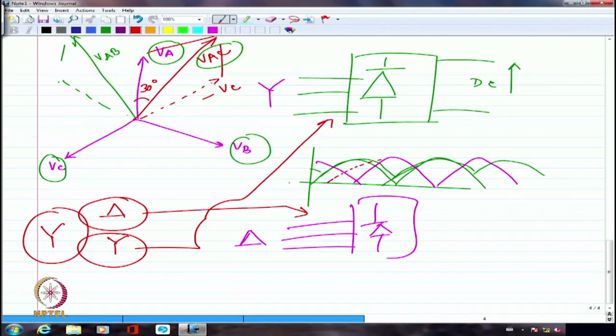So what will happen? They will have voltages which are 30 degrees shifted from each other. Of course, I have to take care of the turns ratio. If I don't, one voltage will be 1 by root 3 times the other, which is not right - I want the same voltages, but shifted 30 degrees from each other.